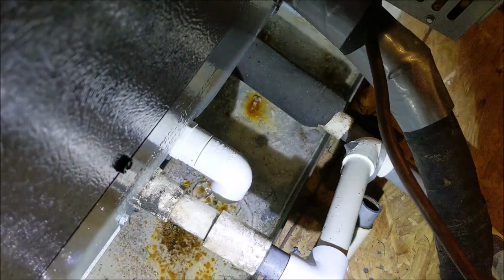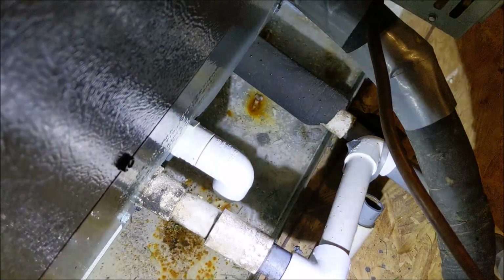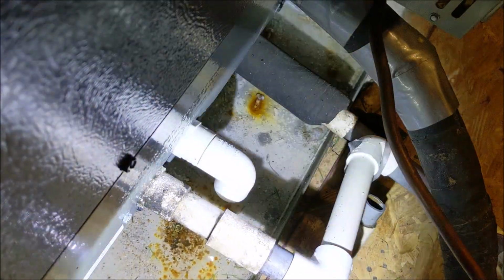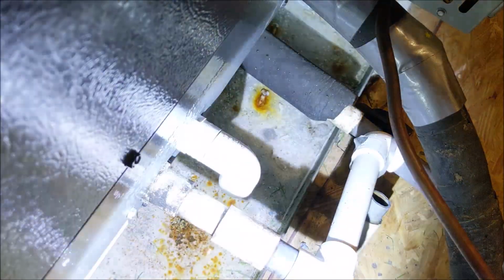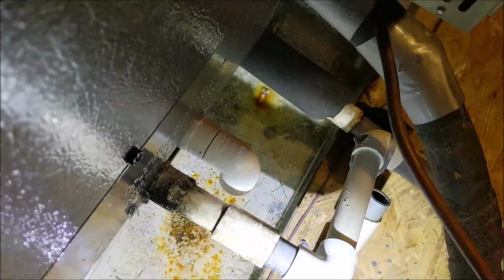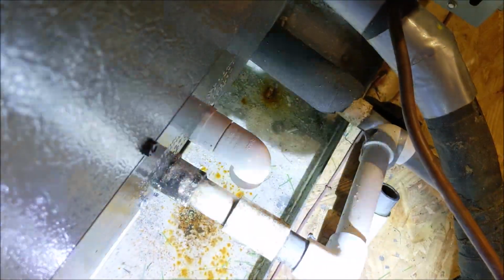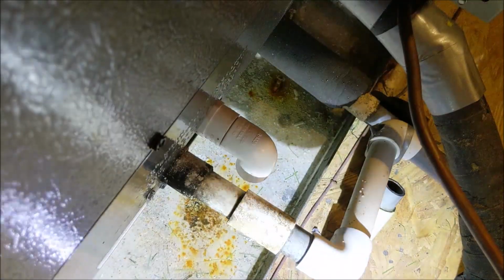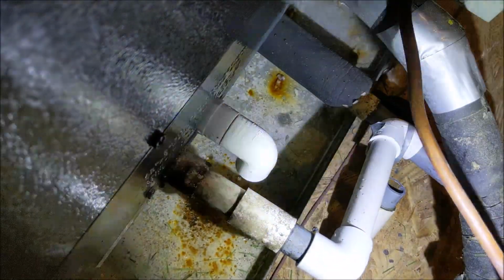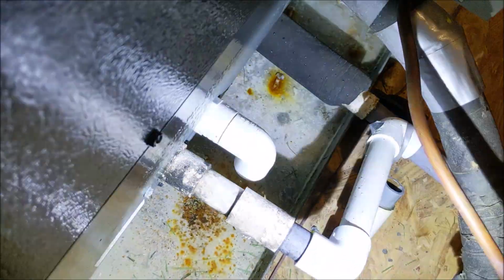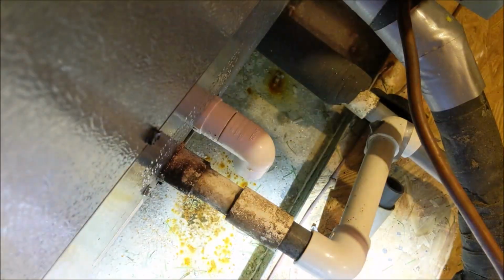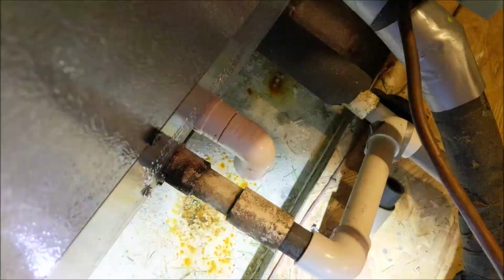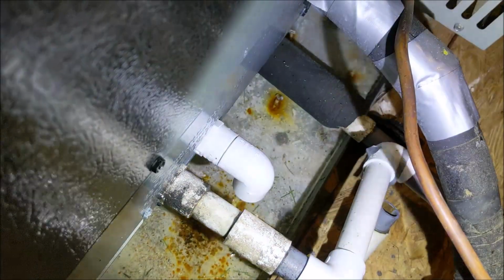What you would have, though, is a hot house, and then you go find out what's going on, and you realize, oh, it's clogged, and it was just a float switch shutting it down because it's clogged. Have it serviced and cleaned. So that's what I recommend: vacuum this out, have the AC cleaned, blow the lines, service the lines, insulate this, install a float switch. So he's got a little bit of work to do, but not too bad.